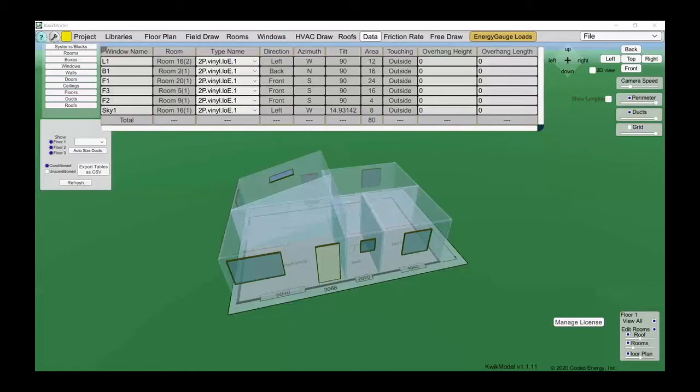I think California can say 50% or more is a window. Yeah, for energy code compliance, if the door is more than half glass, you draw it as all glass. It counts as all glass. And the reason is because when you go and buy a French door, it's tested just like a window. It's tested like an off-the-shelf window.